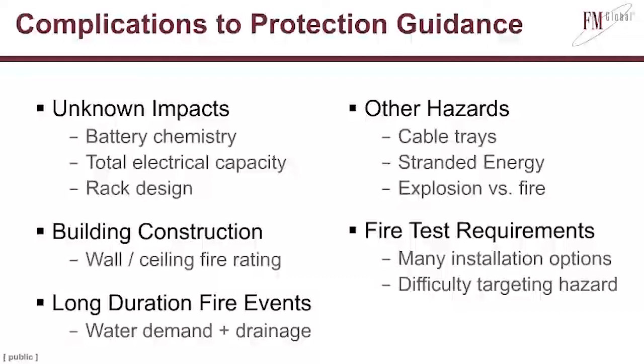I think it's important to realize that you could take the same energy storage system that was tested for one type of deployment and have to run a separate fire test on that same system for a different deployment, because you might be looking at different acceptable exposure hazards or different protection options in place, and that can actually drive you to need to test the same system multiple ways.